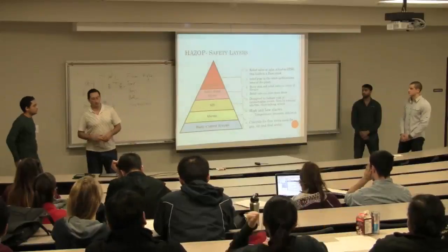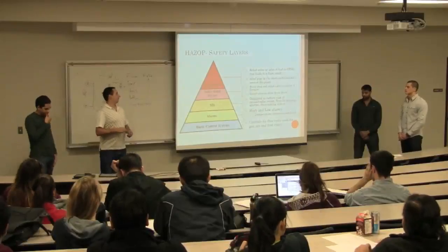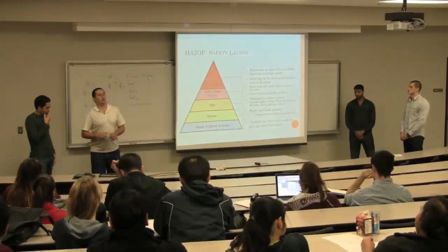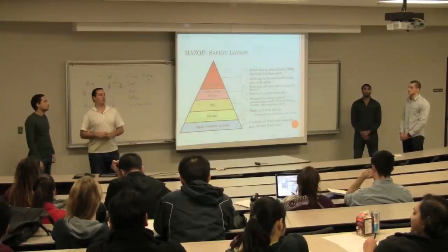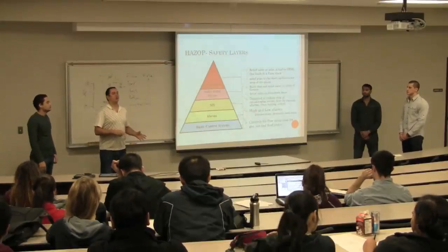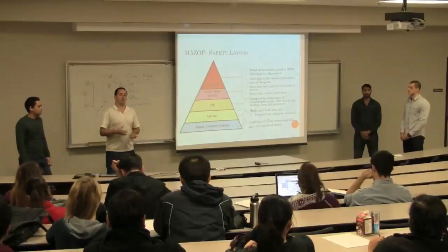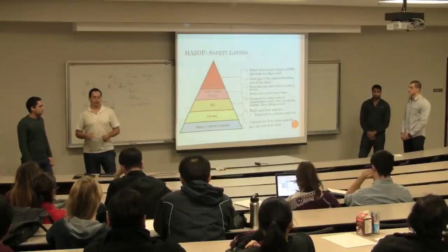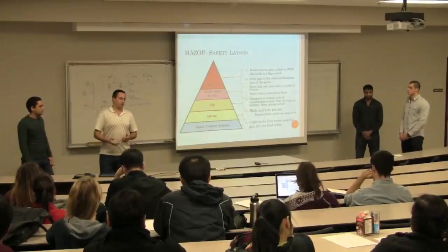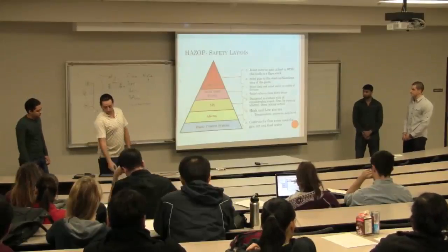safety relief systems which relieve pressure in the system, along with a containment vessel of a flare stack. We did look at the worst case scenario where there are valves and pumps coming from the fuel source, and if you were unable to turn that off, you still need that fuel to go somewhere, so we set up a bypass system with a pressure release disc, and that way it would send it off to a flare stack if it was impossible to turn off the fuel.